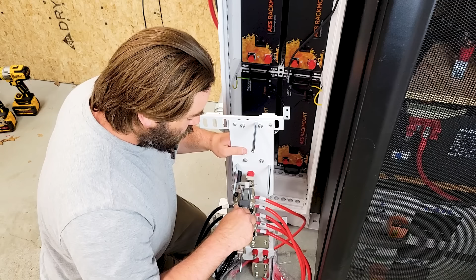Let's get a measurement on them, see how big they are. We've got 14.92 millimeters - let's move that, get another one - 14.97, so I think we can call that 15. And this dimension, 25. These bus bars are 15 by 25 millimeters, so 375 millimeters square cross section. So definitely they can handle the 500 amps continuous that this cabinet is rated for. These bus bars are really large and beefy.